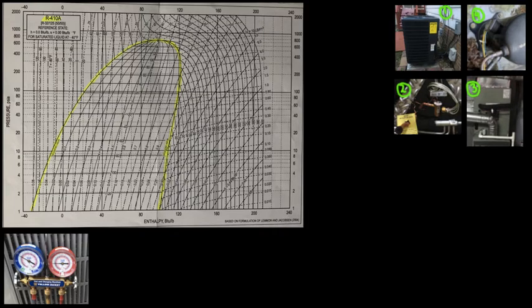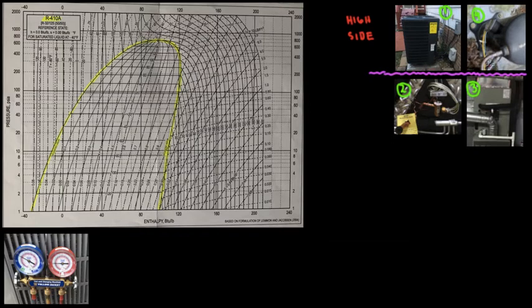We're going to draw a line dividing the system and use a red color for the high side. Why is it called the high side? Because it's high pressure — the compressor makes sure of that. And why is it red? Because that's the convention we use with the gauges. When you connect the gauges to the condenser, you have a red color, which means high pressure and therefore high temperature.